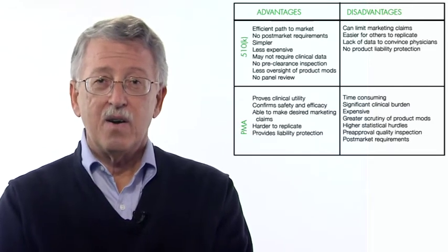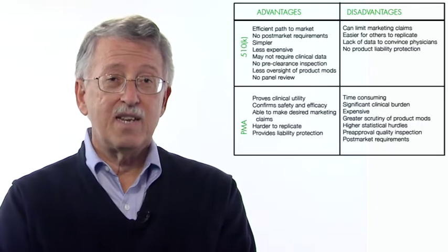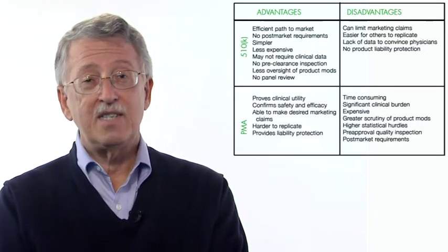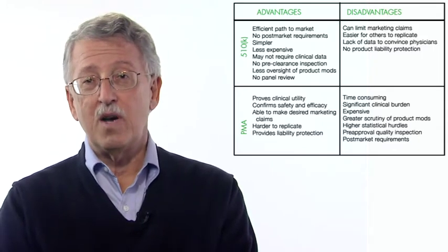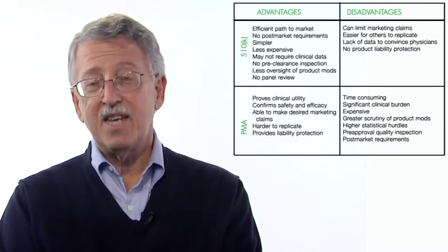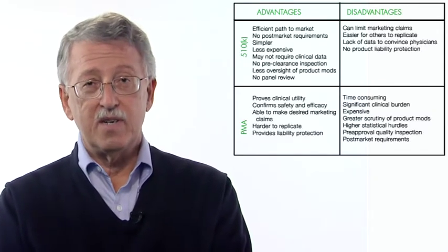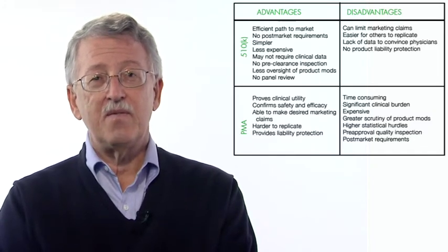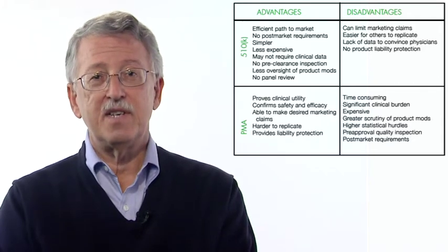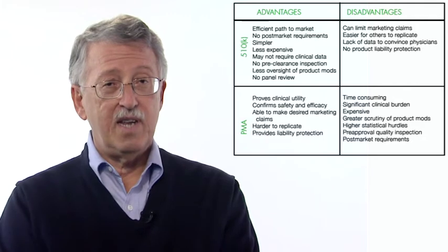On the other hand, there are a few negatives as well. The decision is based on substantial equivalence, and that can limit what you can say about your product compared to other devices. It's easier for another company to come along and make a Me Too submission with respect to your product. The 510K itself, because it often doesn't require clinical data or more limited clinical data, may not have enough information associated with it of the type that users and clinicians would like to see. And there's no product liability protection associated with a 510K clearance.